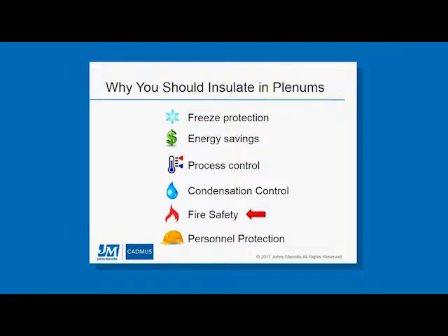There are a number of reasons that we insulate. In a plenum space that might not have conditioned air in it, and so is subject to the climatic conditions outdoors, we might have to insulate for freeze protection for some of the water piping, maybe sprinkler piping. Energy savings and process control: we put a lot of energy and effort into being comfortable within our buildings, and so we want to be as efficient as possible and save energy by insulating those various systems within a building. Condensation control is a concern in plenum spaces for non-conditioned air, where you might have below-ambient air piping or ductwork that might be subjected to hot and humid conditions where condensation might occur.